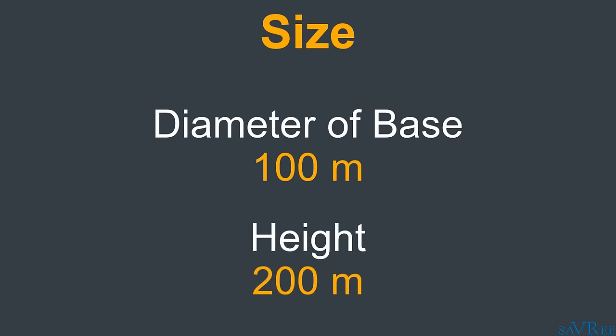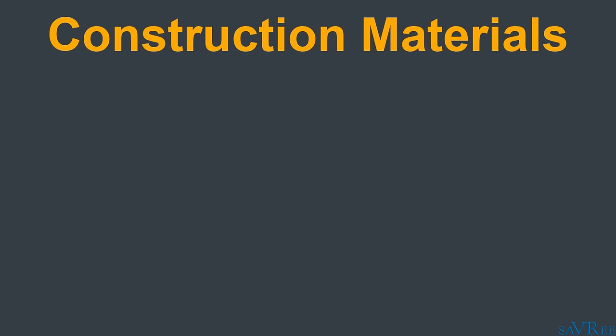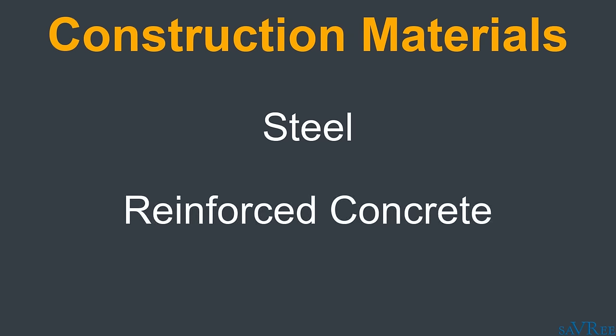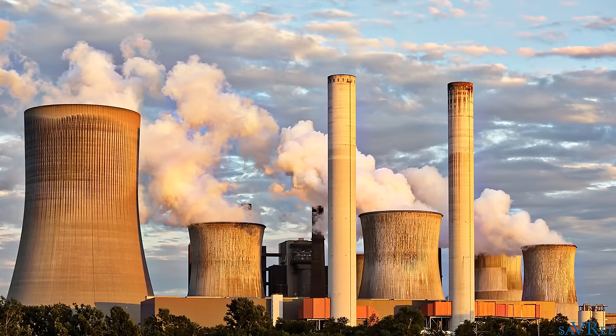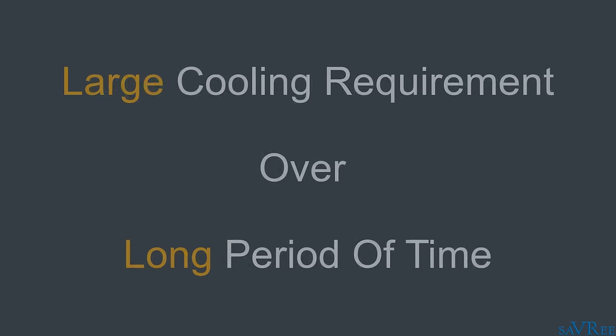Typical construction materials for natural draft cooling towers include steel and reinforced concrete. Typically, you're going to see them next to thermal power stations, for example, coal-fired power stations and nuclear power stations. That is simply because natural draft cooling towers are very expensive to construct, and they're only ever used where you have a large cooling requirement over a very long period of time, for example, 30 years. You will not see these towers being built and put into service for only two or three years. It just doesn't make economic sense.